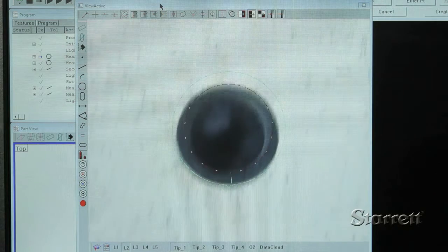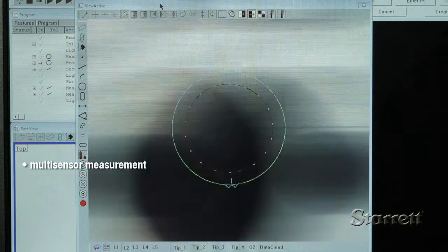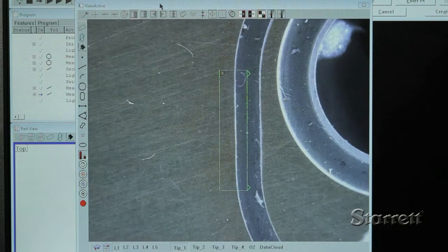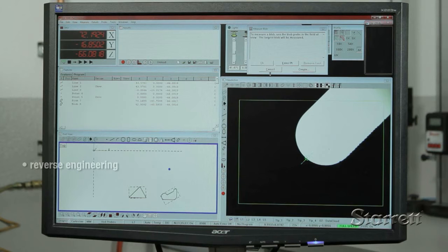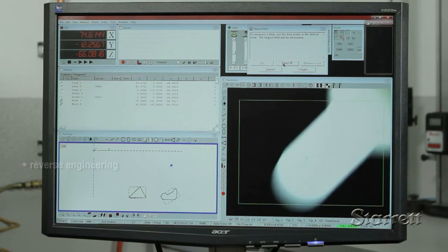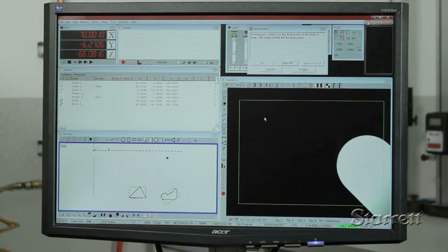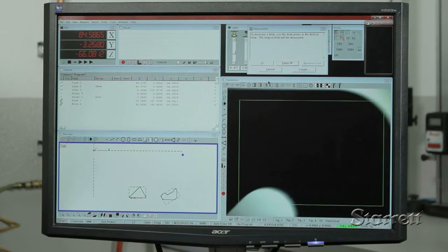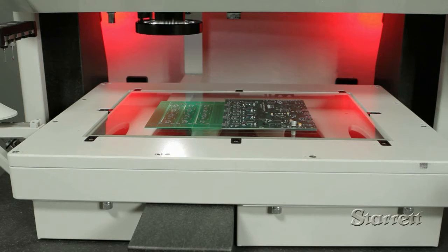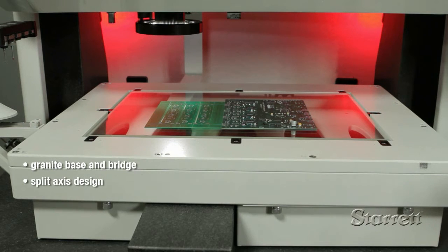Laser sensors are ideal for gathering data points on non-prismatic surfaces. Some parts can best be measured by combining video measurement with either touch probe or laser. In some applications, all three might be utilized. LF systems have even been used for reverse engineering, collecting dimensional data from a combination of its sensors to create a DXF CAD file.